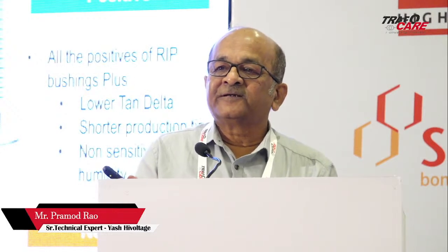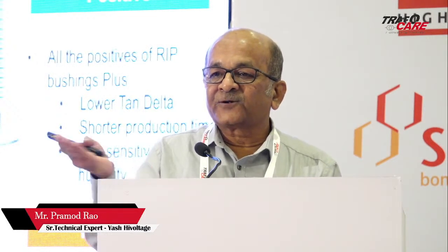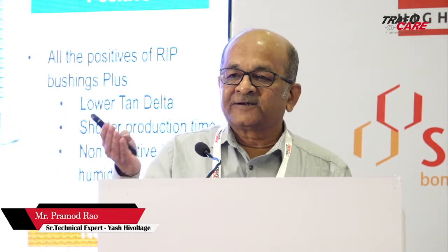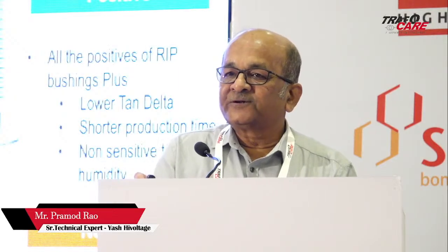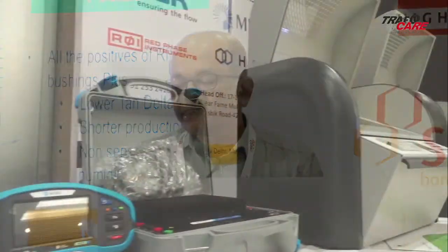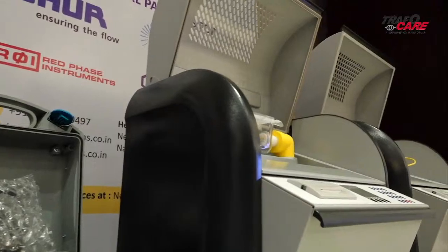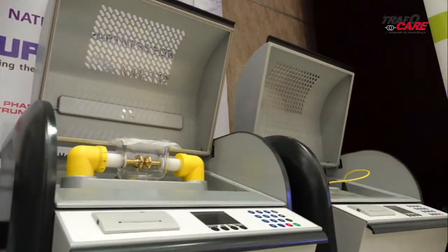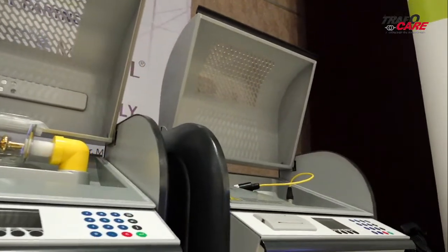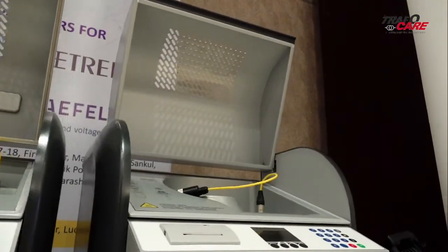Excellent aging experience because it is a solid insulation. Then the bushings can be mounted in any position. It can be mounted horizontally also. We rarely see it in India, but in the international context, it is horizontally mounted as well. Another benefit is that this particular resin we are using is a Class E insulation. We can operate up to 120 degrees centigrade.